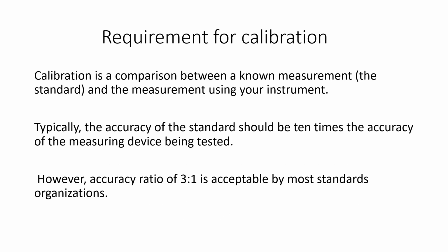Requirement for calibration. Calibration is a comparison between a known measurement, that is the standard, and the measurement using your instrument, right? So what is required for calibration is that you must have the data or values from your instrument, and the data or values from a standard, or you can say the true value or the standard value, right? So you must have the two things, and then you can do the comparison. Typically speaking, the accuracy of the standard should be 10 times the accuracy of the measuring device being tested. The ideal scenario is that the standard should be 10 times the accuracy of the data of your measuring device, right?